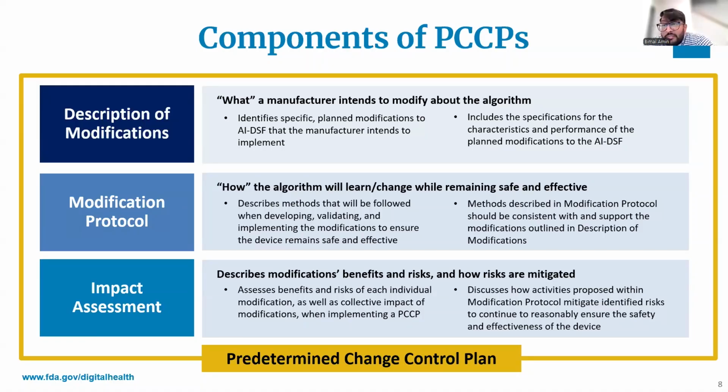The second is the modification protocol. This answers the question, how? How will you develop, validate, and implement those changes in a way that ensures the device is safe and effective? What data will you use? What are your acceptance criteria?